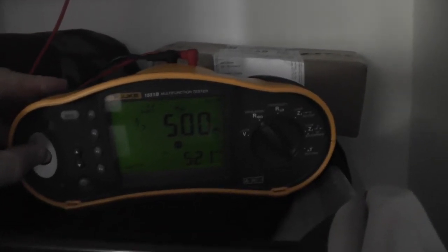So I've found that wiring out. I'll clip the lead to it and do that test again. So great — greater than 400MΩ, so that's good.